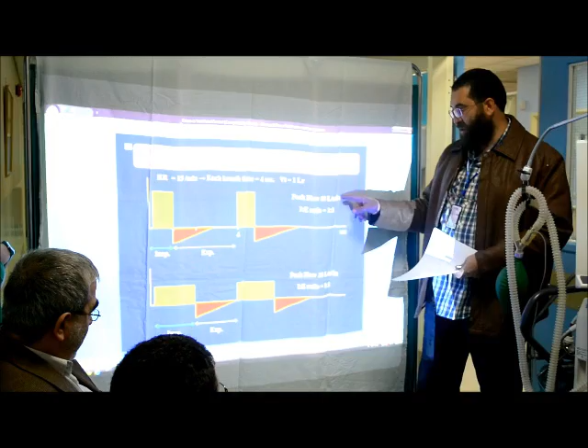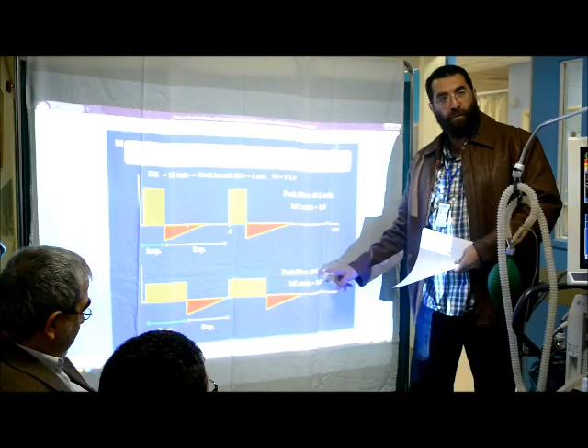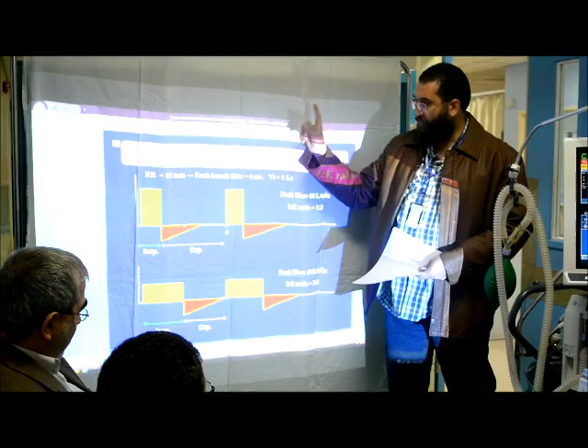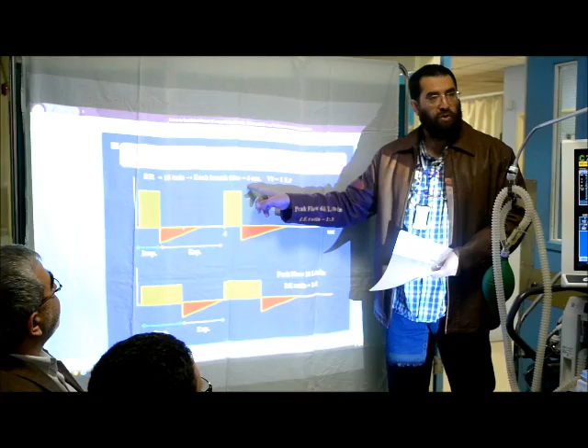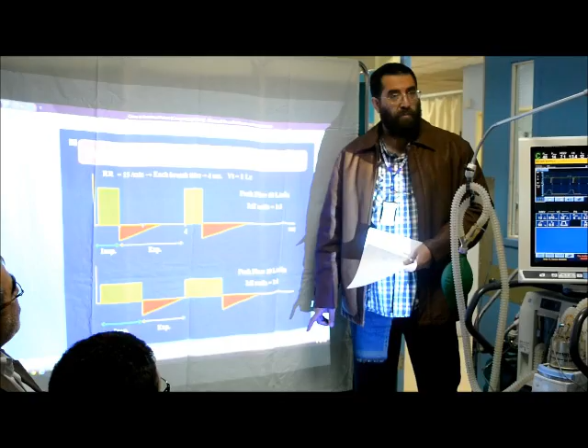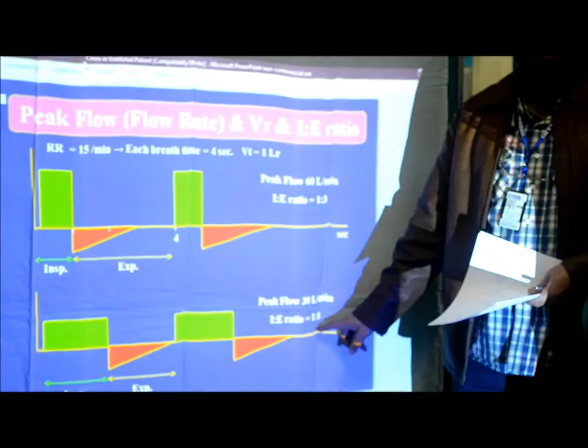Okay? The same example, but we reduced the peak flow. Instead of 60 liter per minute or 1 liter per second, it will be 30 liter per minute or half liter per second. But the same setting: respiratory rate 15, tidal volume 1 liter, and the breath time will also be 4 seconds. So the 1 liter, how many seconds will it take to be delivered? 2 seconds, because the speed is half liter per second and the tidal volume is 1 liter. The breath is 4 seconds, so the remaining expiratory time will be 2 seconds. So the ratio will be 2 to 2 or 1 to 1.